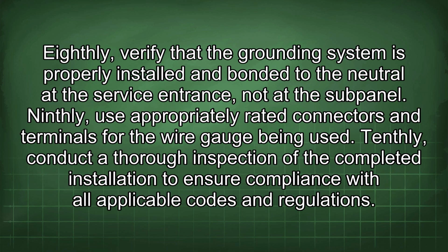Eighthly, verify that the grounding system is properly installed and bonded to the neutral at the service entrance, not at the subpanel. Ninthly, use appropriately rated connectors and terminals for the wire gauge being used. Tenthly, conduct a thorough inspection of the completed installation to ensure compliance with all applicable codes and regulations.